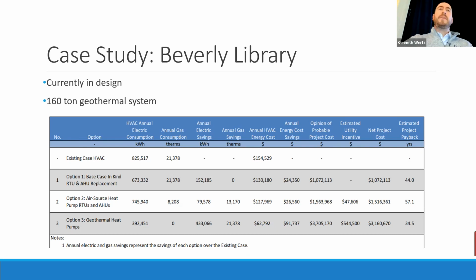So the geothermal well field will last that long. The actual pipes in the ground are supposed to last 50 to 60 years, if not longer. But the heat pumps themselves in the building are not necessarily going to last that long. Those might be 20 years. So that's a limitation of looking at things in terms of payback as opposed to life cycle costs, like Ken mentioned, where you want to factor in that maintenance cost of having to replace a certain number of units every year once you get to 10 to 20 years out.